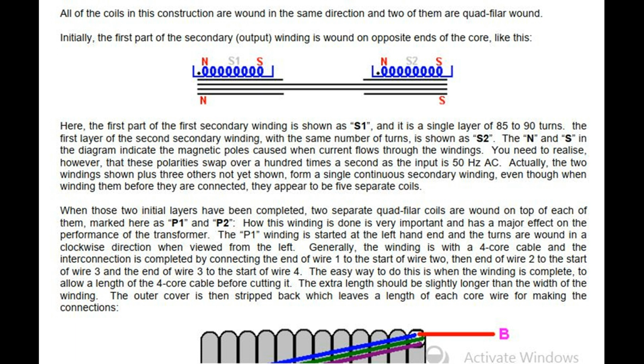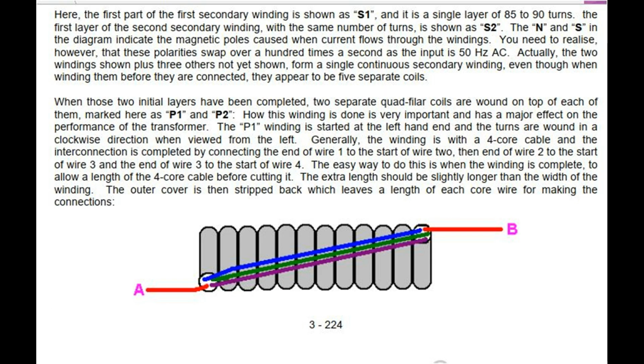When those 2 initial layers have been completed, 2 separate quadfilar coils are wound on top of each of them, marked here as P1 and P2. How this winding is done is very important and has a major effect on the performance of the transformer. The P1 winding is started at the left-hand end and the turns are wound in a clockwise direction when viewed from the left. Generally, the winding is with a 4-core cable and the interconnection is completed by connecting the end of wire 1 to the start of wire 2, then end of wire 2 to the start of wire 3 and the end of wire 3 to the start of wire 4.